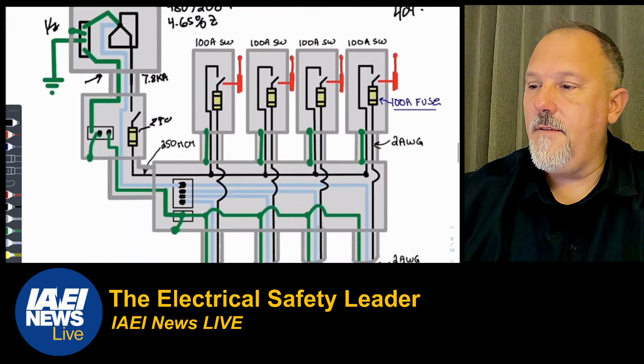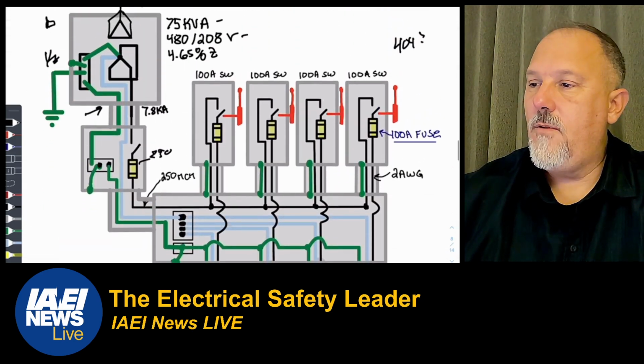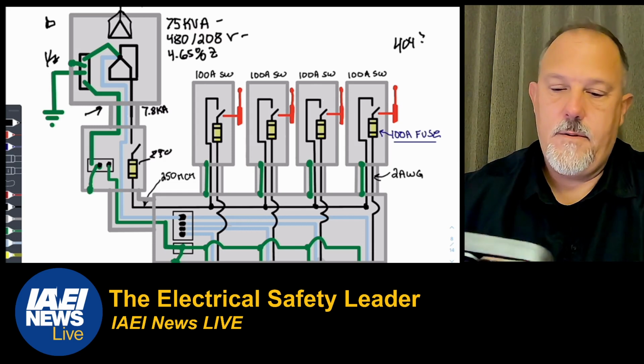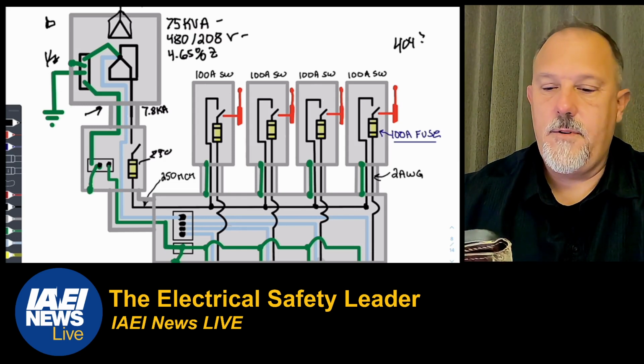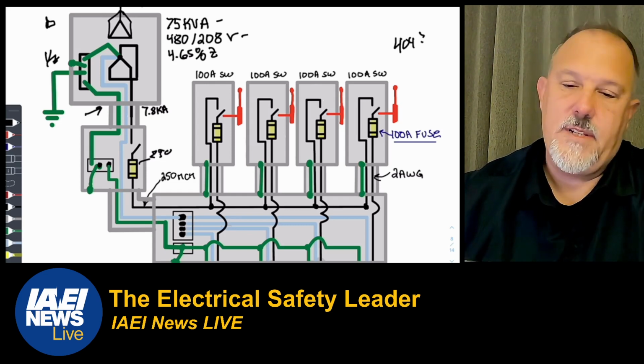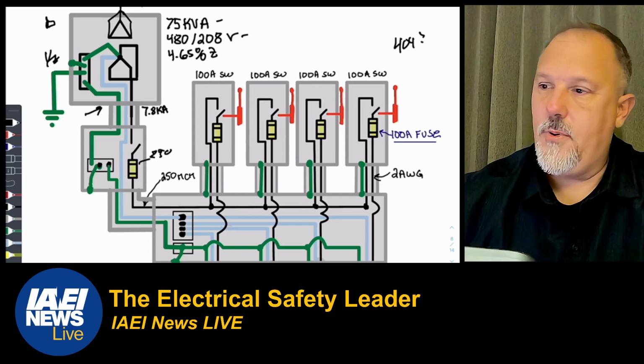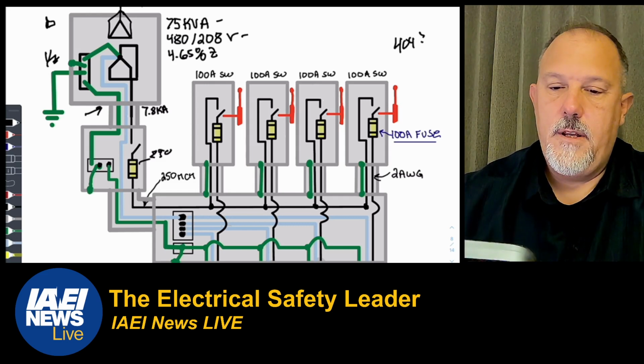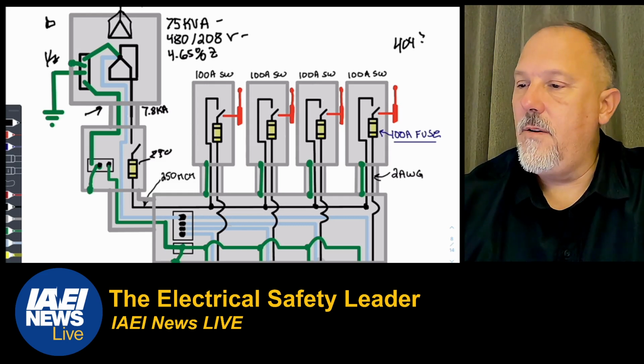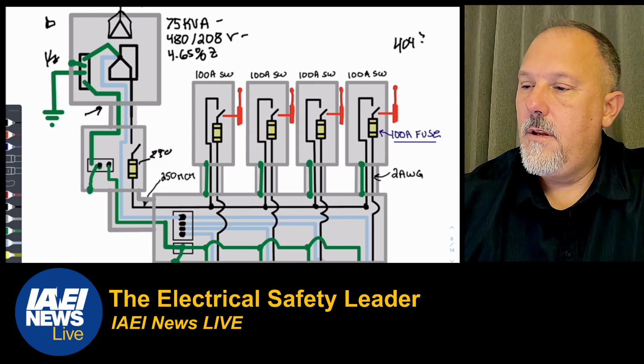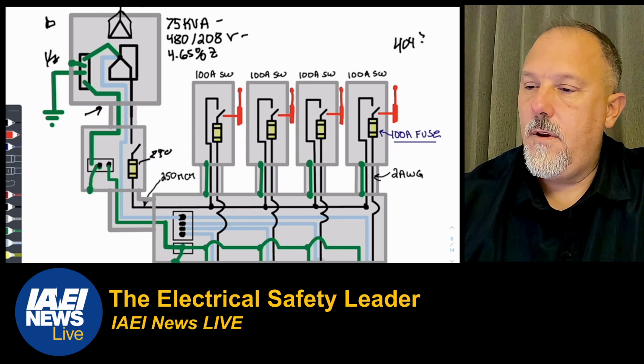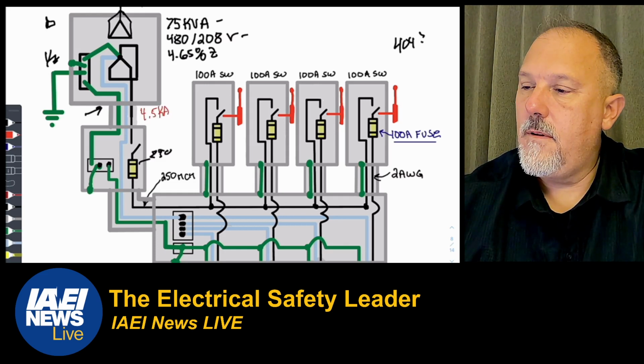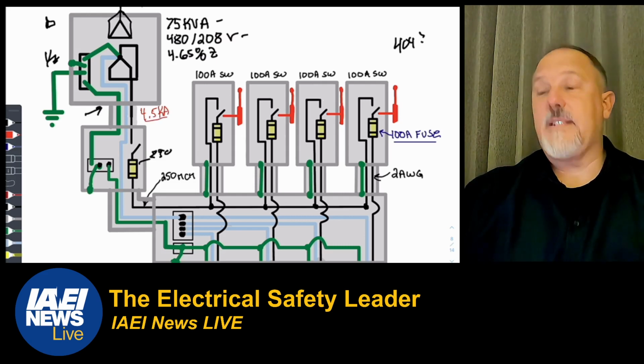That tells you that all of this, 4.65. I just want to double check. 75 times 208 divide, 3 square root divide, 208.1792. And then I divide that by 0.0465 is 4,476 amps. So I'm going to write it as 4.5 kiloamps. That's what's available at the secondary of that transformer.